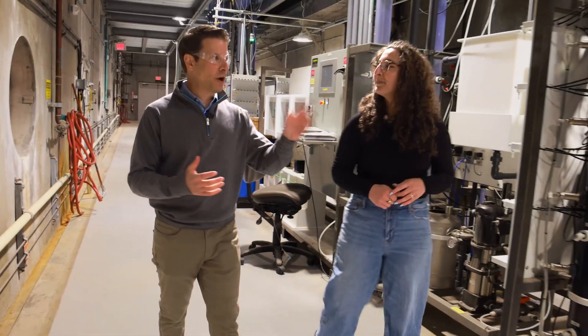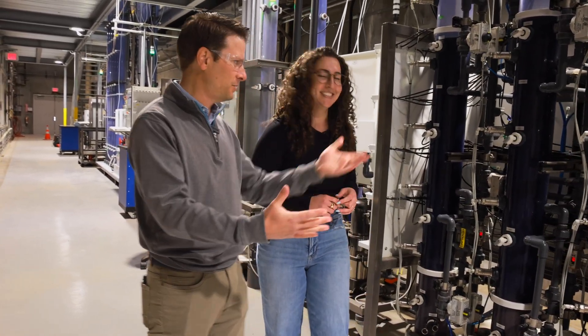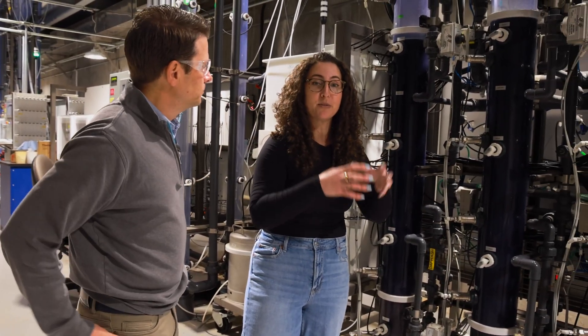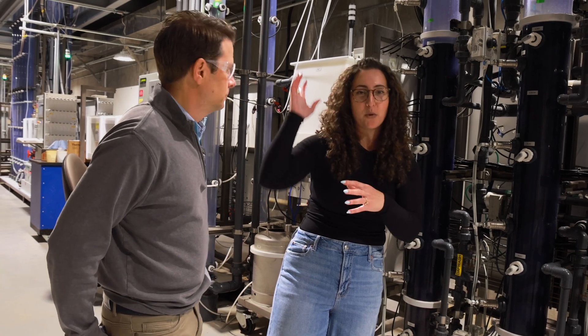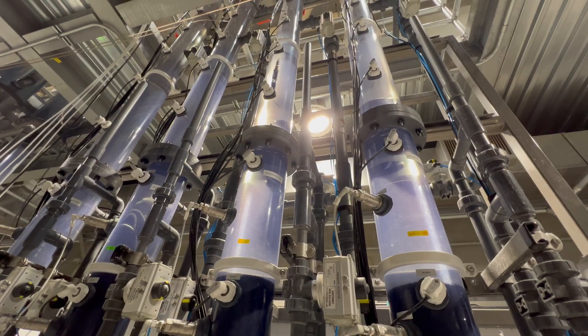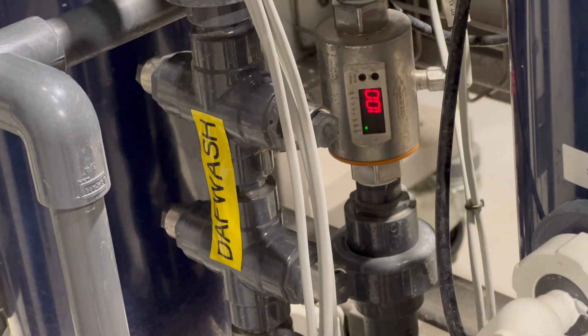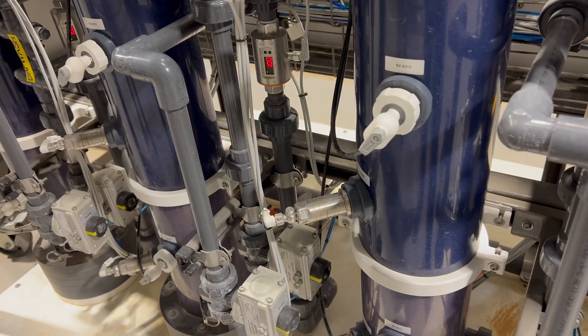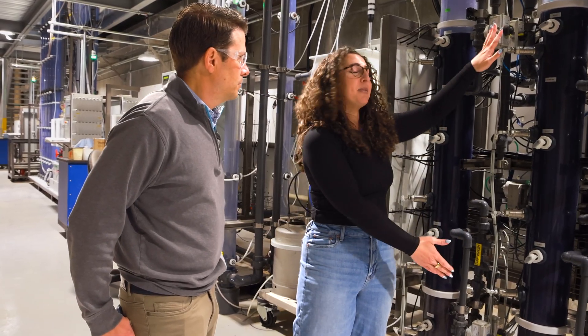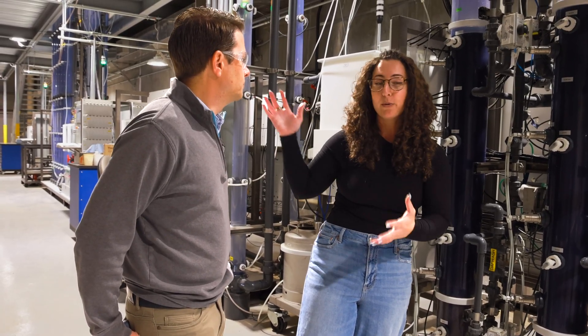The last step in the treatment process in our mini plant and our big plants is filtration. Small scale here, we do it on a much bigger scale at AMS. This is our filters — where we're going to remove all those large floc particles created in coagulation flocculation. You pass the water through, those flocs get stuck in the media, and coming out is your particle-free, clean water. The filter media here is the exact same as we use at full scale — anthracite, which is a carbon-based compound, with sand at the bottom. This depth is the exact same depth used at full scale because we want to be as exact as possible when simulating full-scale scenarios.